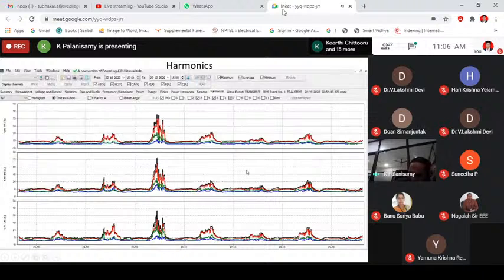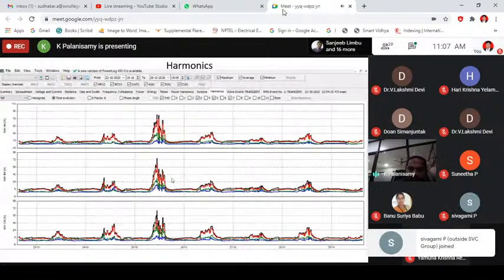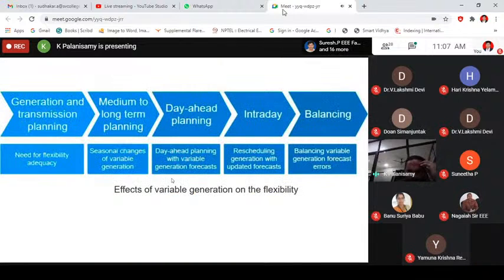And the other issue is, fortunate or unfortunate, your solar PV inverter will supply only pure sinusoidal current with a unity power factor. But most of the loads are non-linear: VFDs, ASDs, your UPS, your LED lights, many things are non-linear loads. So those non-linear devices require non-linear current, right? So what will happen because of that? Since the solar is supplying pure sinusoidal current, the entire non-linear current must be drawn from the grid. So the THD drawn from the grid is increasing. This is how the harmonics will increase, because the solar is supplying only pure sinusoidal current and the rest must be drawn from the grid. So all those things are issues.